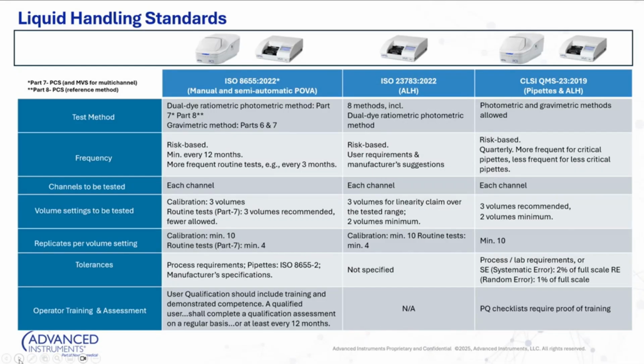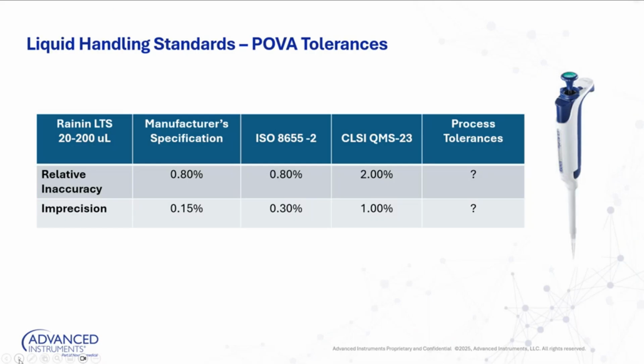They don't give you much detail about that, but really where all the detail comes into play is the ISO standards. So let's talk a little bit more about tolerances. This tends to be a bit of a hot topic for us. So let's take, for example, you can see on this particular slide I have depicted a Rainin LTS pipette. It's a 20 to 200 microliter single channel device. Now, with regards to ISO, as well as CLSI, they have some recommendations, but let's take a look at this very first column, which is the manufacturer's specification.